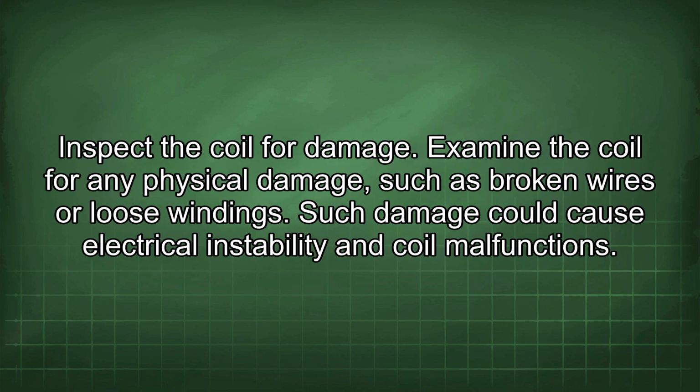Inspect the coil for damage. Examine the coil for any physical damage, such as broken wires or loose windings. Such damage could cause electrical instability and coil malfunctions.